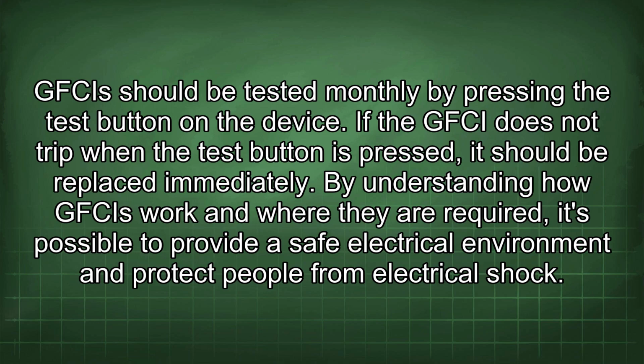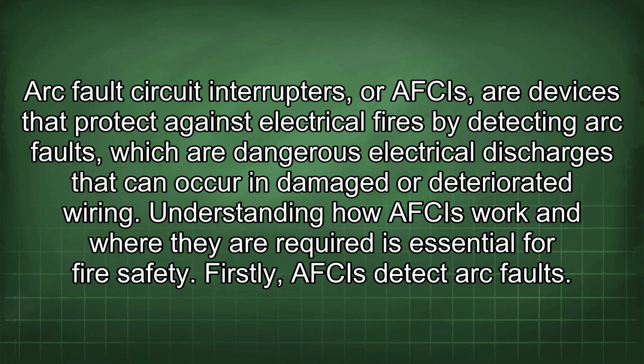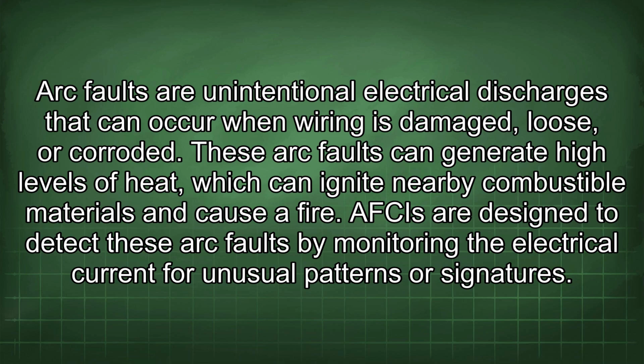Arc fault circuit interrupters, or AFCIs, are devices that protect against electrical fires by detecting arc faults, which are dangerous electrical discharges that can occur in damaged or deteriorated wiring. Understanding how AFCIs work and where they are required is essential for fire safety. Firstly, AFCIs detect arc faults. Arc faults are unintentional electrical discharges that can occur when wiring is damaged, loose, or corroded. These arc faults can generate high levels of heat, which can ignite nearby combustible materials and cause a fire. AFCIs are designed to detect these arc faults by monitoring the electrical current for unusual patterns or signatures.